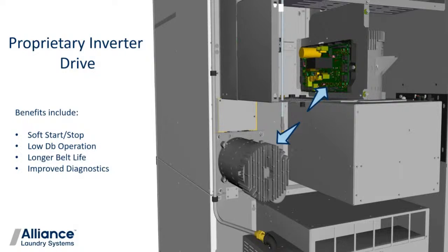But this brings something else to the table that a lot of people don't think about, and that is improved diagnostics. When you have an inverter control, like we're showing with the arrow pointing up there, this actually acts as a monitor for the motor now too, and it actually acts as a monitor for the incoming power to the machine. So by monitor, I mean if the belt ever slipped off or something like that, which is very uncommon, but let's say we had a belt problem or one of the pulleys bearing got seized or whatever, the inverter can actually read the amp draw through the motor and determine that if there's a problem, like, hey, this is way too easy, there must not be any tension, we must be missing a belt. Or the flip side of that, we've got a seized bearing on an idler shaft, or the shaft itself is actually seized. Sorry, there's no bearing. And we have too much pull, it can see that too. So that's really neat, and it translates directly to the front end control and gives us an error code.